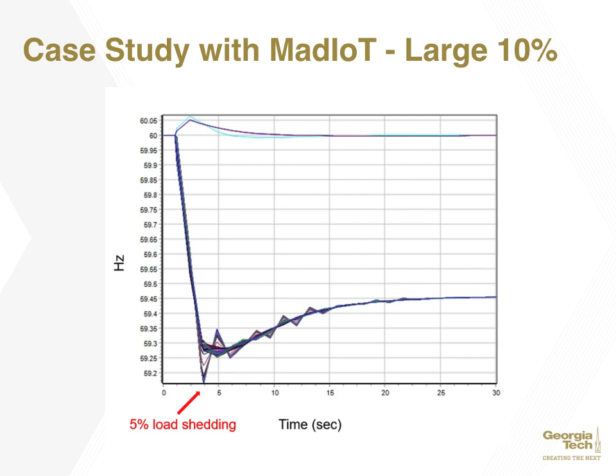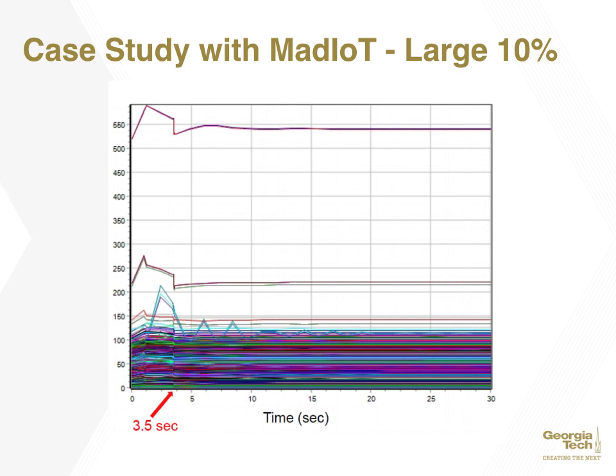In the next scenario, the attacker now has 10 times the compromised devices, 8 million, causing an increase of 10%. Now the system frequency goes down to a level where under-frequency load shedding takes over and corrects the system, as seen in the 1% scenario. As with the power output, there is a spike due to the attack, but it's quickly mitigated within seconds, thanks to the protections in place.